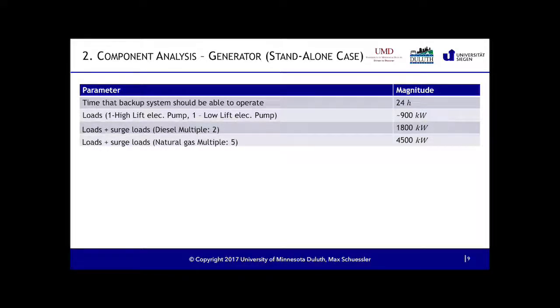And then the options were natural gas and diesel generators, and those are two really different things to look into, because diesel has a higher energy density as a liquid, which means that when I need to supply torque to start my pumps, I need less rated power for the diesel generator. On the other hand, natural gas has a lower power density, which means it can supply less torque at the same power rating as the diesel generator, so my natural gas generator has to be quite a bit larger in rated power than the diesel generator.